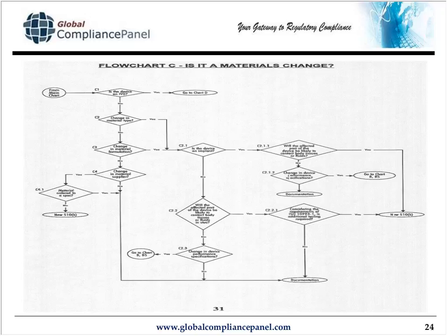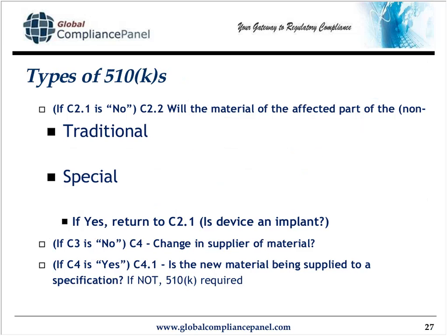But if I am not an IVD, C1, not changing the material type, not changing the material formulation, and not changing the material supplier, I can just do it internal. There's nothing that requires me to submit a 510K in that situation.